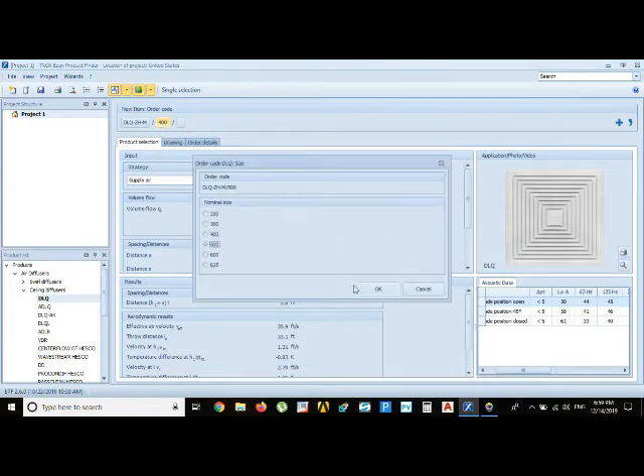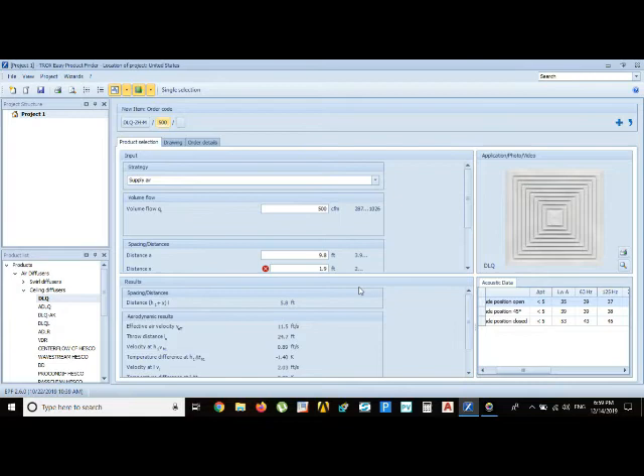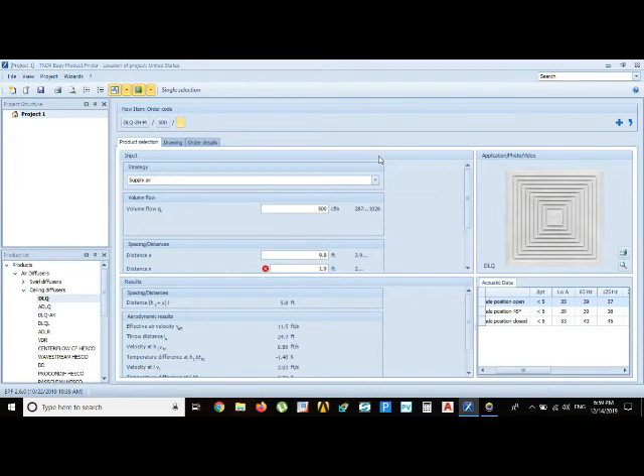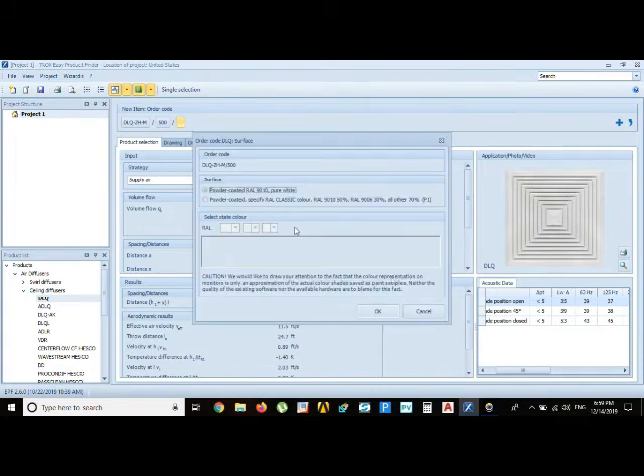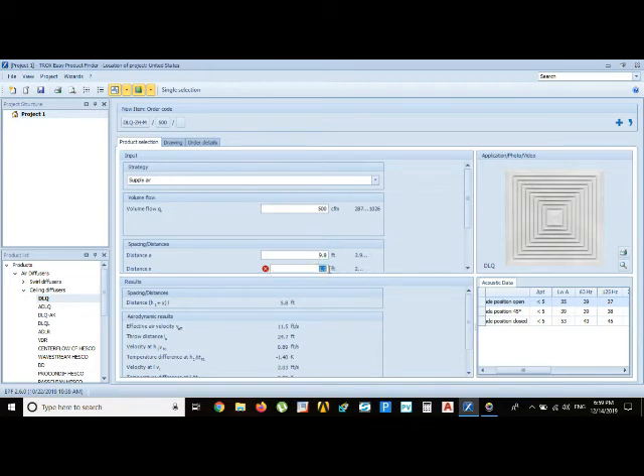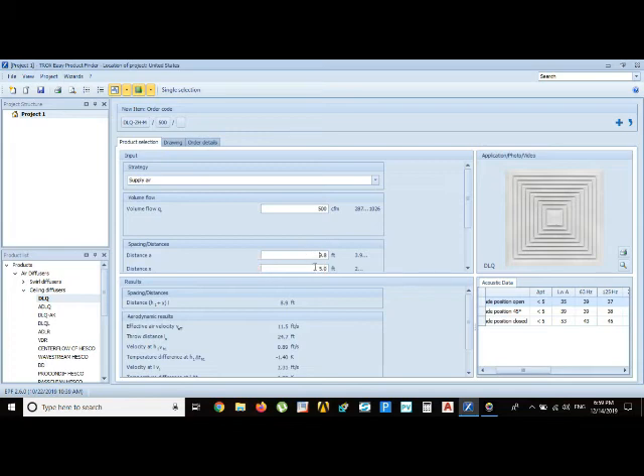Now select the 500. In this case you can see the 500 CFM can pass through the 500 by 500 diffuser. Here it's powder coated, RAL 9010 pure white, etc. Here you can see distance 0.9 feet is very low. Just change this to 2 feet, it's also low. 5 feet, 5 feet is enough because when you install two diffusers 5 feet apart.